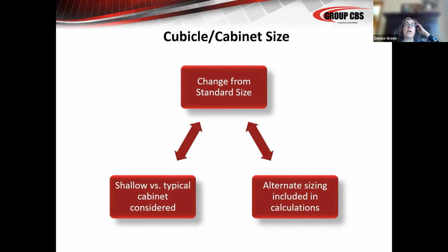So if you're going from the old calculation of a 20 by 20 by 20 cabinet to a Magnablast cabinet that is 36 by 42 by 75, you're going to have probably a little bit lower incident available energy as far as blast goes. Your distance might be a little bit further because there's more area, more volume for that arc flash to go. It doesn't all come out at you. Some of it goes toward the back. Conversely, if you have a disconnect that is 38 calories and it's only 8 inches deep, if that label were to be recalculated, it's very likely that that would exceed the 40 calorie and make it unsafe to operate. So training your people to know that cabinet size can affect your existing label is really, really important.